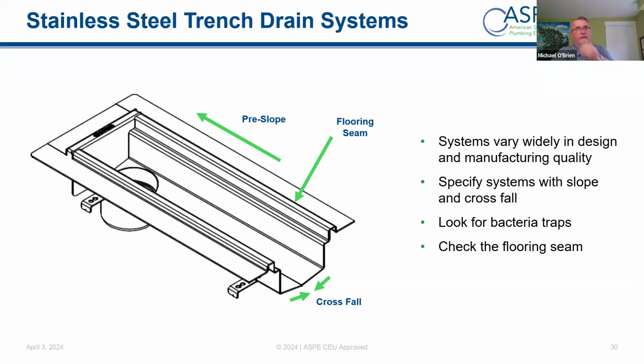So look for cross fall in the channel. Look for a pre-slope. Look at how they're tied together if they're longer runs. Look for sharp angles, interior crevices. There shouldn't be anywhere where dirt can get stuck and become a breeding ground for bacteria.